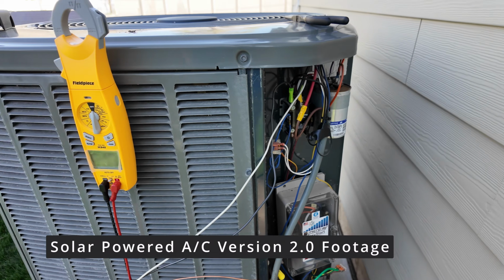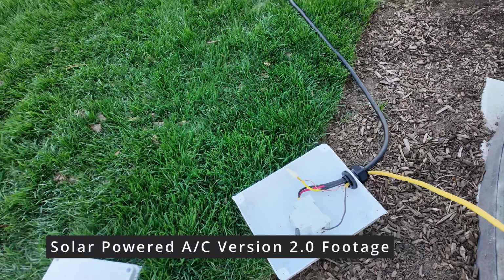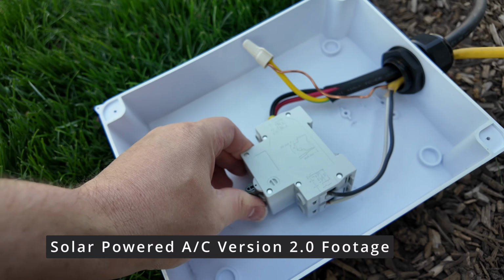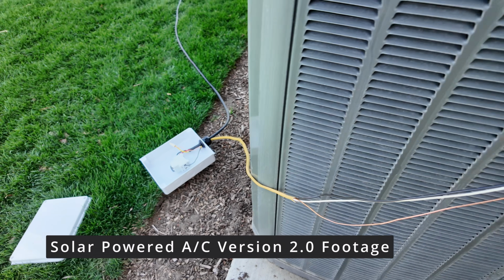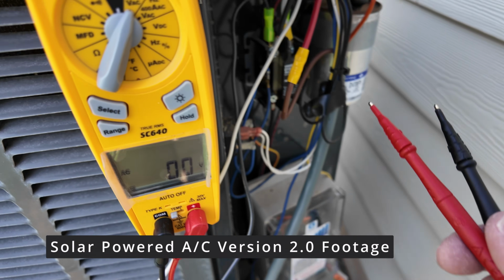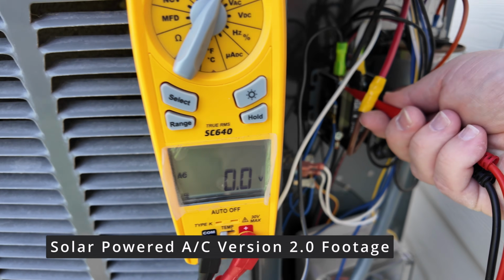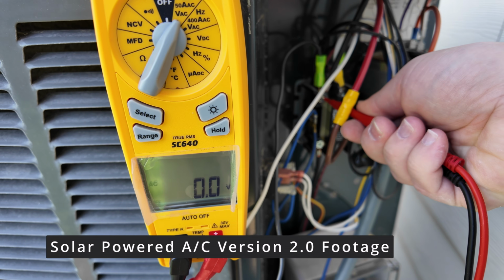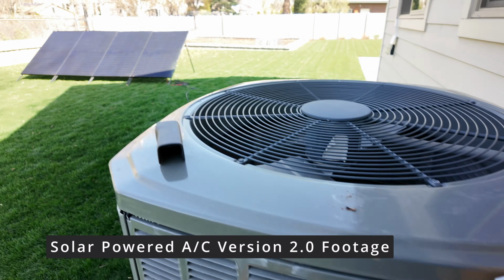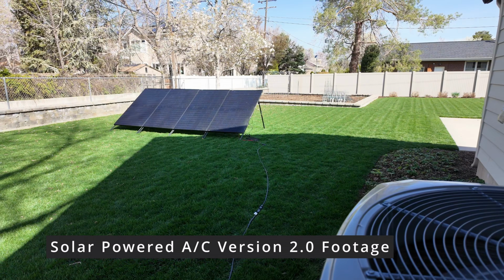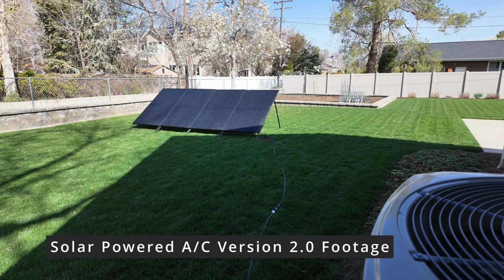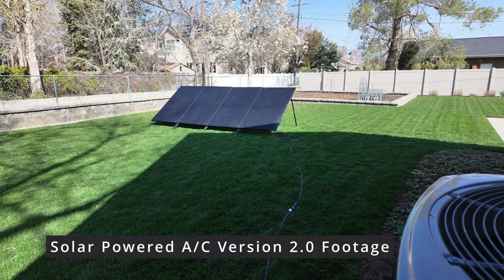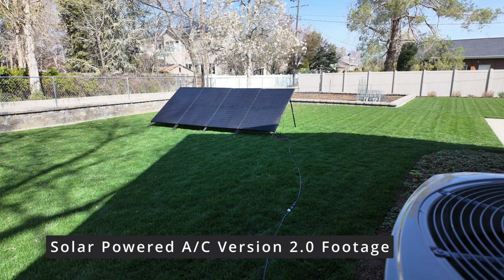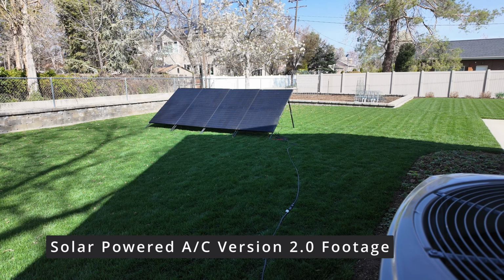All right, now with that wired, we can come over here and we can go ahead and energize the breaker here. And I'm going to show you, even with that breaker on, there's going to be no power here. Let's take this multimeter and check, and there's no power. That's because that microinverter will not produce any power until it sees grid power. It's equipped with rapid shutdown technology so that it shuts off and stays off while there's no grid power available.